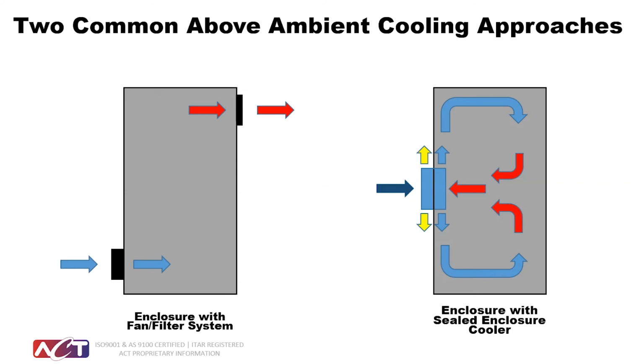The diagram on the right shows the airflow of a sealed enclosure cooler. Hot air on the inside of the enclosure, which is shown as red arrows, is impinged onto the heat exchanger fins. Heat is removed from the airstream and the air is circulated back to the enclosure, as indicated by the light blue arrows. At the same time, outside air enters the opposite side of the sealed enclosure cooler, as shown by the dark blue arrows. This air passes through the heat exchanger fins, picks up heat from the inside, and carries it away from the enclosure as illustrated by the yellow arrows. There is no cross-contamination of the internal and external air streams.